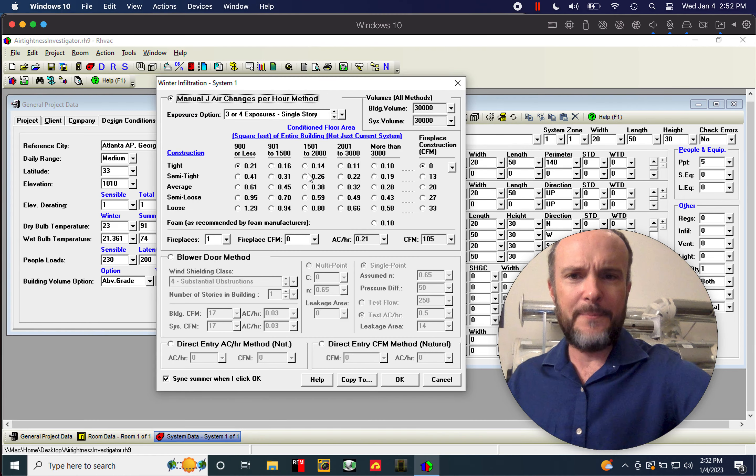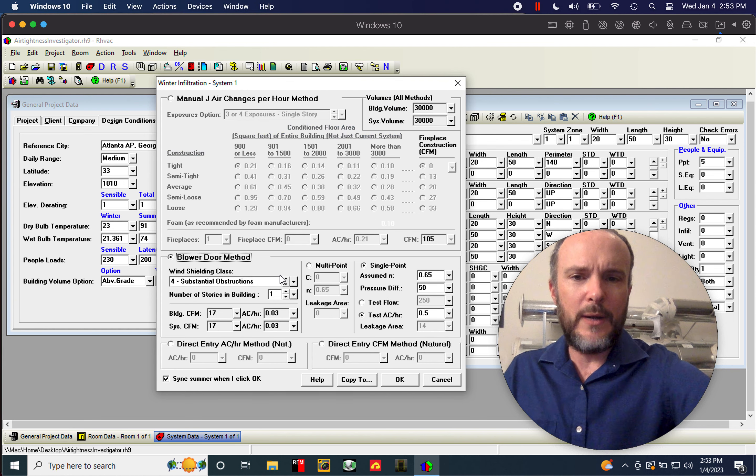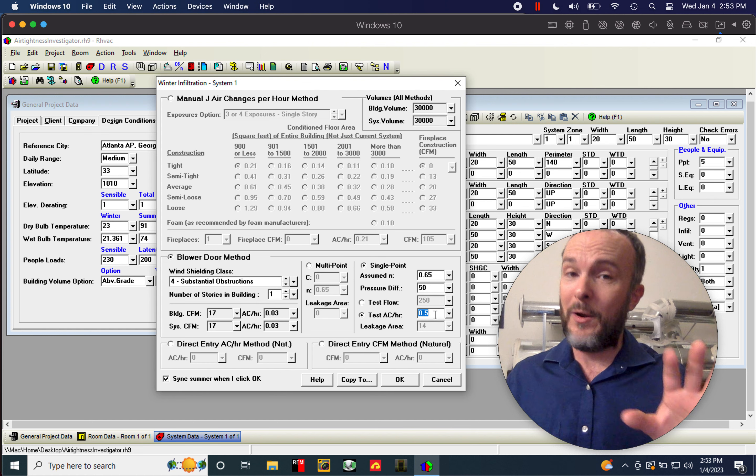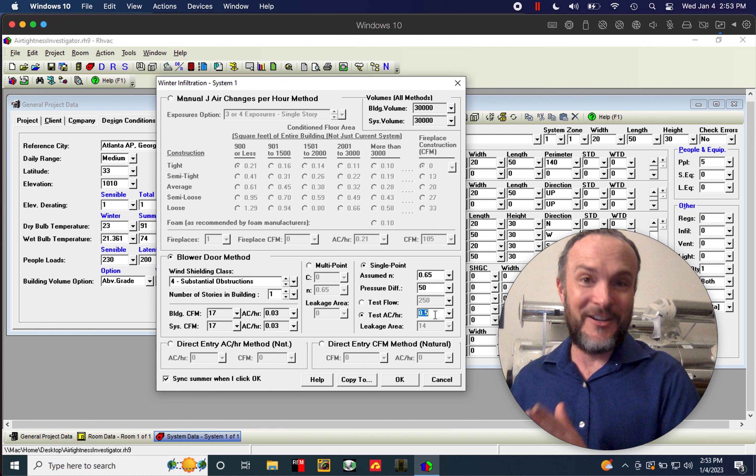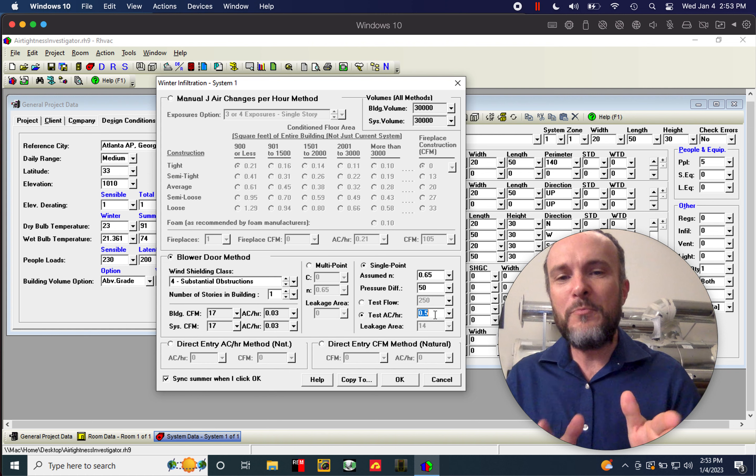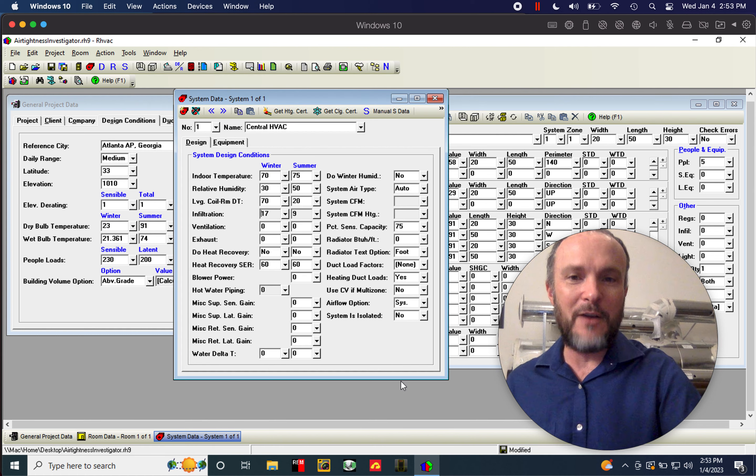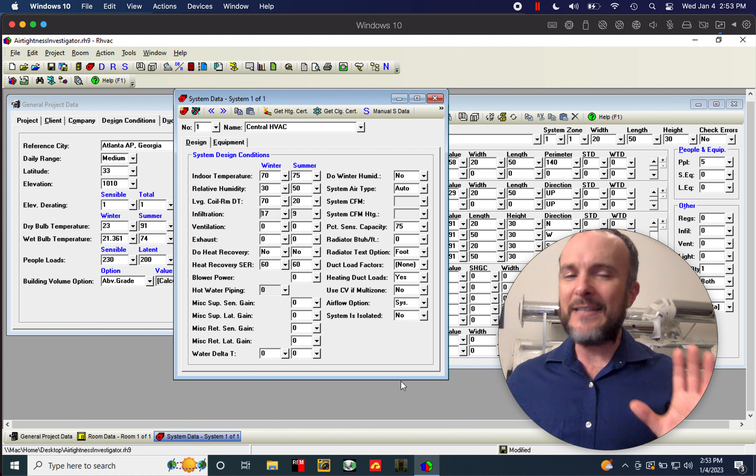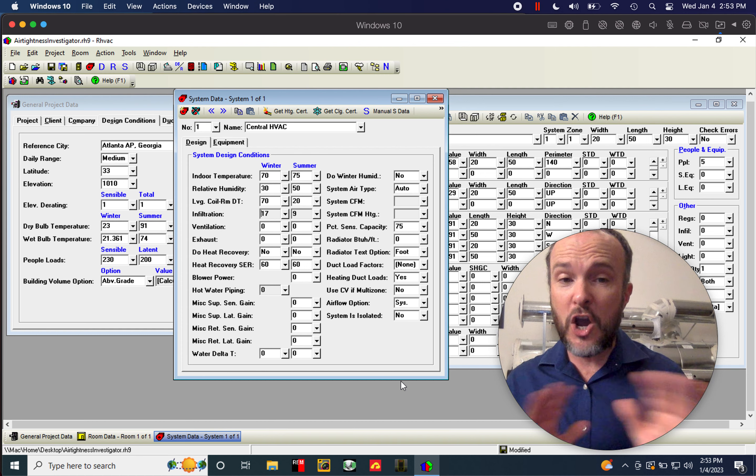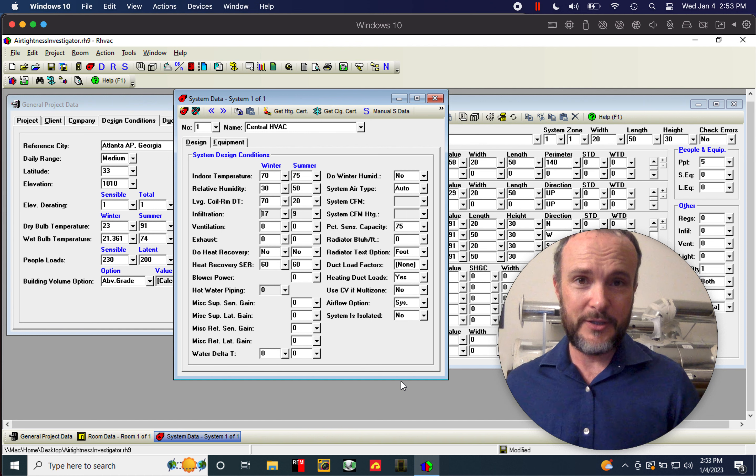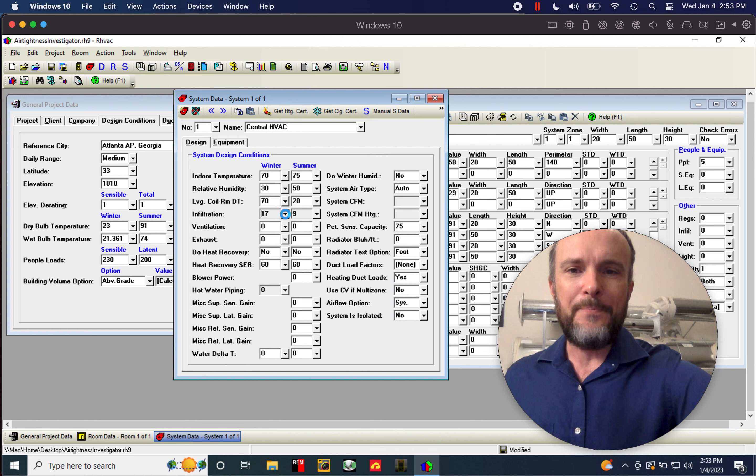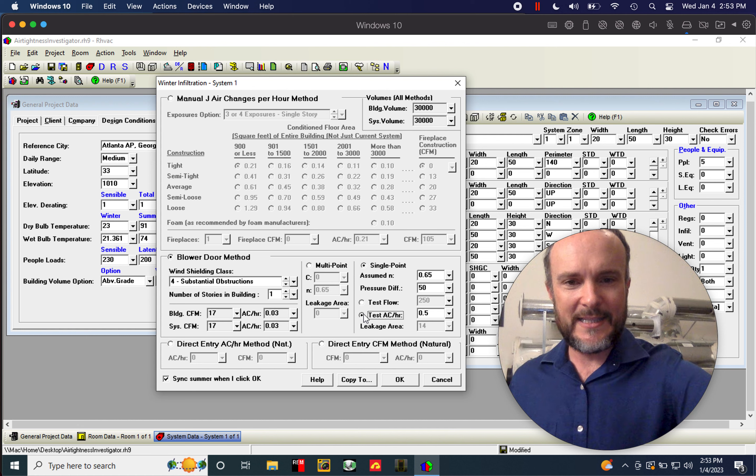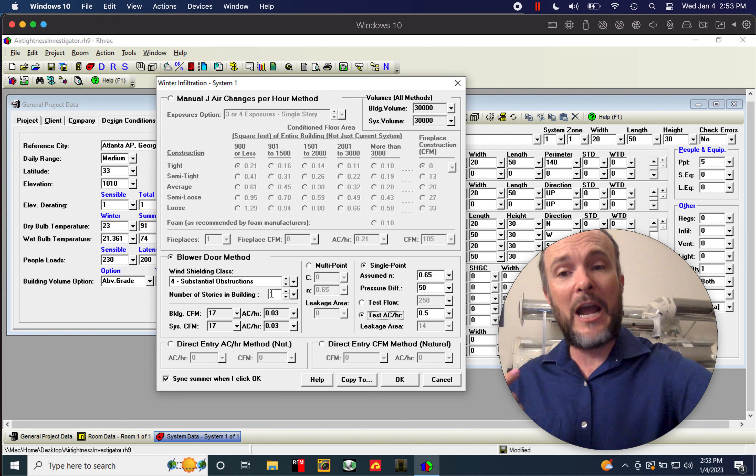When we go back over, I'm going to delete that. When we go back over here, you can see that the blower door, I'm just going to explain this real quick. If you were to put in the test ACH 50, which is, well, I'm going to get into how to estimate this in a second, because knowing how to do that is the second part of the battle. But if you put in the ACH 50 and you just hit okay at 0.5, it will now set that as the value that will show up by the way, in your report that you run as basically zero CFM in the wintertime and summertime. So there will be no air leakage showing up in any of your loads on the rooms. And that's okay. It basically rounds down because it's so minimal.